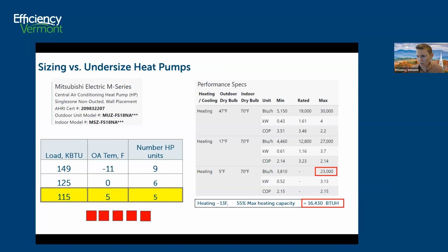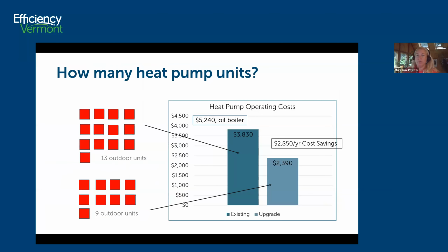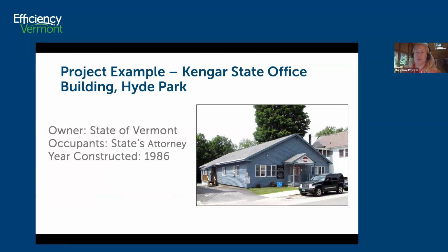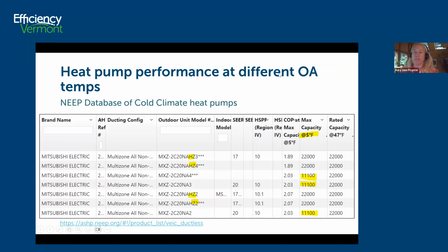And then another question: undersizing units for heating, via fewer units or lower efficiency units, could translate to higher electric usage during lower temps. Is that correct? Well, certainly it's not necessarily going to be higher electric. You're going to have more fossil fuel. There was one slide that shows the coefficient of performance, 1.89 versus 2. So at 5 degrees, it's not horrible. It's still pretty good. And for units that can still have good capacity at 5, you're not really paying much of a penalty. So yes, it's a difference of maybe 1.8 versus 2, but you don't dip down below 1.5.